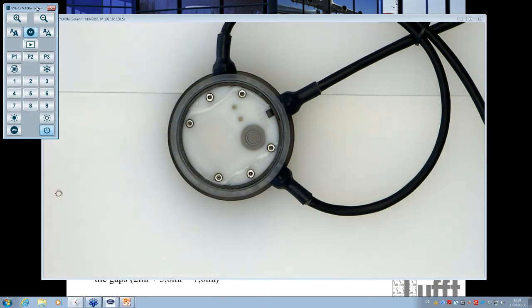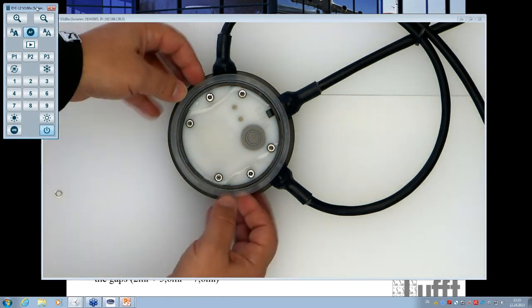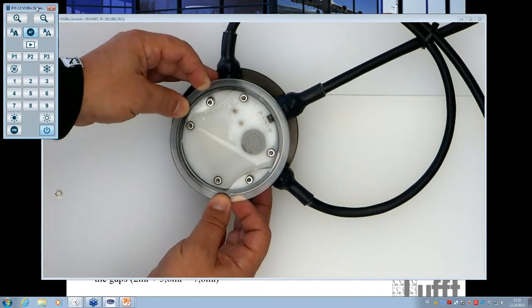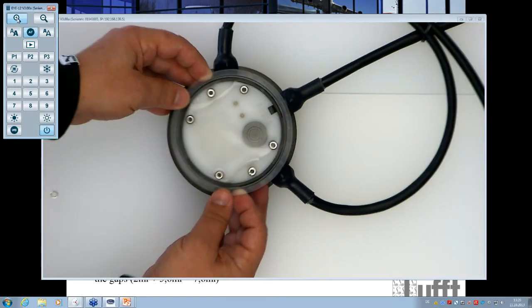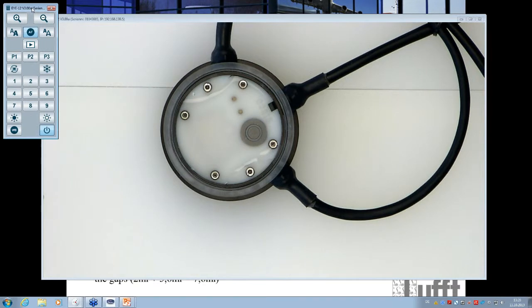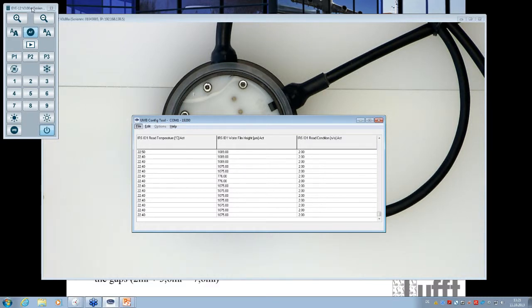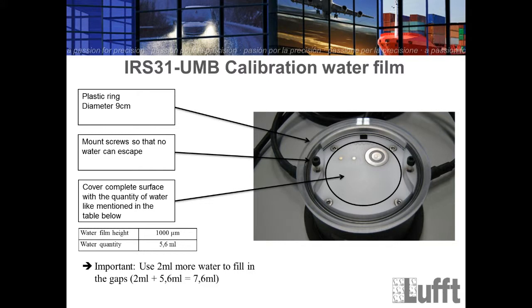And what will happen if this sensor is not really flat in the street? For example, I will show you that now, something like that. You see that the water will flow down. Well, on the other side, it's the same thing. And then the value will not be representative anymore. So normally, to check it, you need to have a flat built-in sensor on the street. That's really important. If it's a little bit not flat in the street, of course you can also do the calibration here, but maybe you will get some wrong value, so you have to know it. All right? So that's the first measurement here, and now we have about 1075 micrometers, which is not bad. All right? I hope that is clear now. All right? So we will go to the next step.